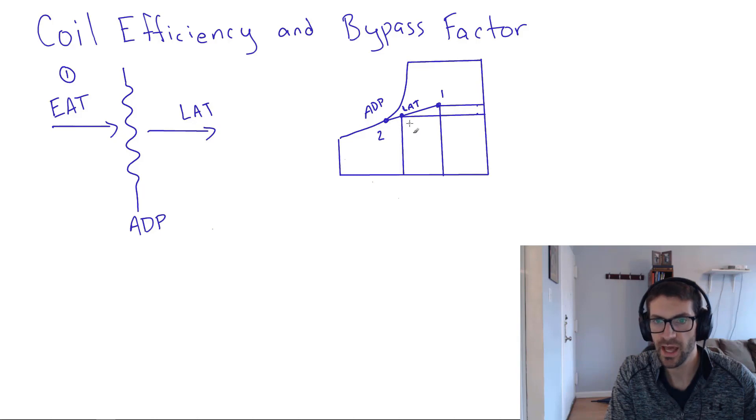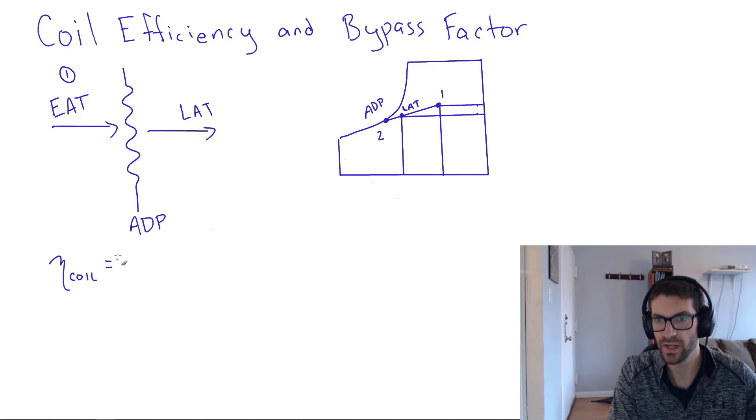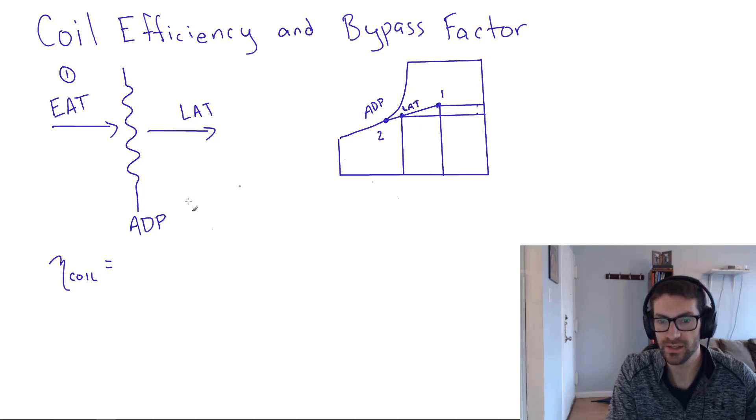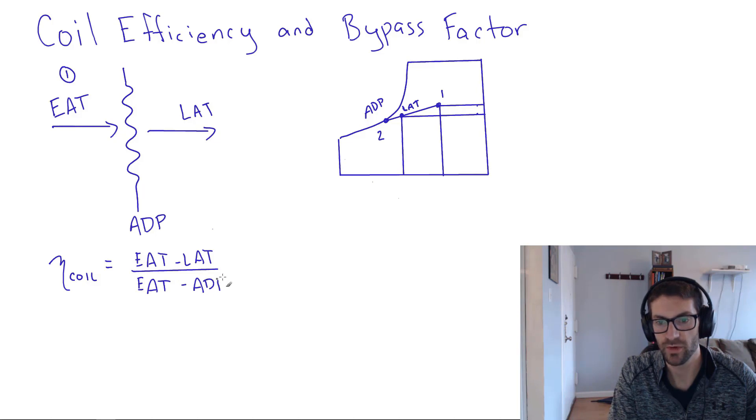So how do we actually calculate the coil efficiency? The efficiency of a coil is given by the ratio of the temperatures. You can also do ratio of humidity ratios, although it's less common. So the delta T that we're actually seeing is going from entering air to leaving air as compared with the delta T that we could be seeing, which is the entering air minus the ADP. That would be a ratio that would equal one if it was 100% efficient coil.